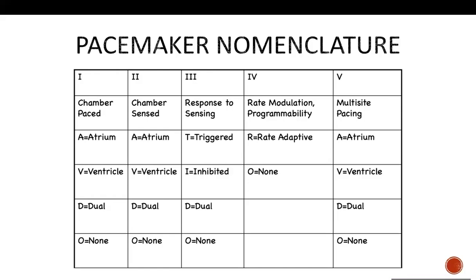So if you're talking about shocks, the pacer function or the pacing is different than the shock algorithm. So even if you pace VOO, that means it's not going to inhibit pacing if there is noise, but the device is still going to see any noise. Changing the pacing modality in a defibrillator doesn't inhibit the shock. But you have to turn off the defibrillation portion of it, regardless of what the pacer function of the device is. Okay?